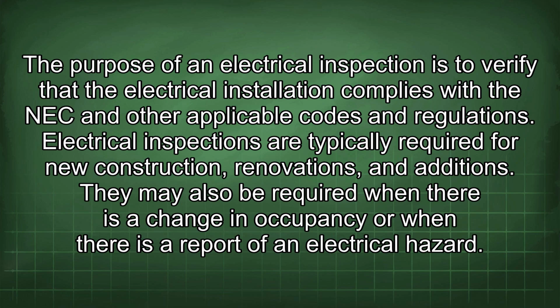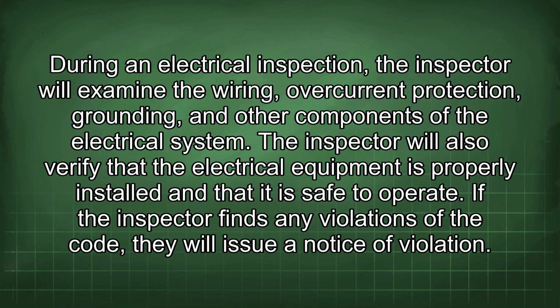They may also be required when there is a change in occupancy or when there is a report of an electrical hazard. During an electrical inspection, the inspector will examine the wiring, overcurrent protection, grounding, and other components of the electrical system. The inspector will also verify that the electrical equipment is properly installed and that it is safe to operate. If the inspector finds any violations of the code, they will issue a notice of violation.